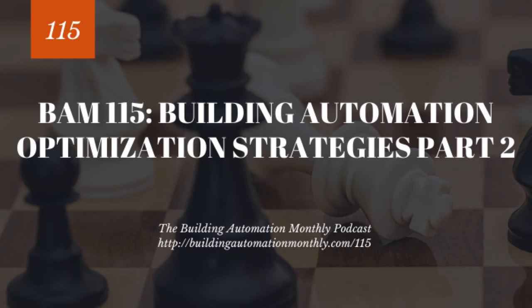Because remember that moisture in the air contains BTUs, and the higher the relative humidity... a relative humidity of 80% at 90 degrees is a lot more moisture than a relative humidity of 80% at 50 degrees, because as air gets warmer, its capacity to hold moisture gets higher. That is why folks feel really muggy at 90 degrees and 80% relative humidity, but 55 and 80 is not as bad, because essentially you have grains per pound of moisture.